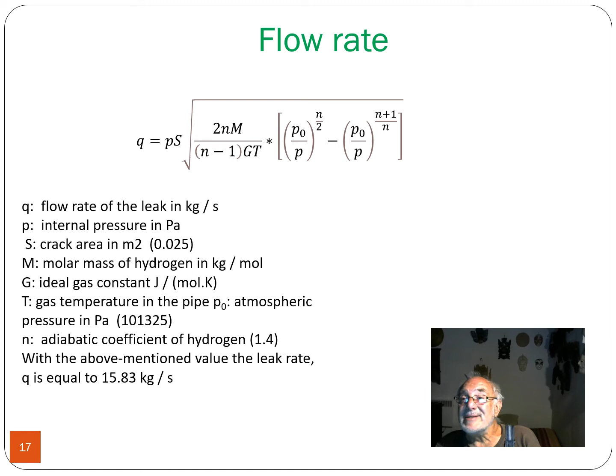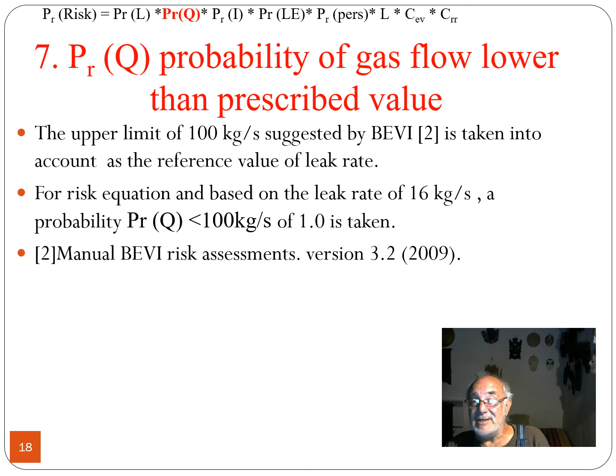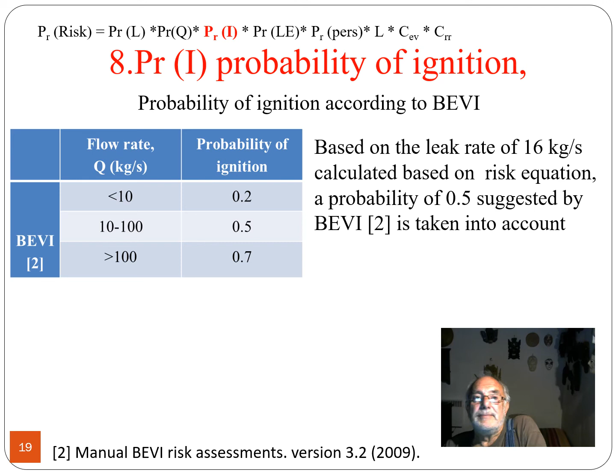Now we compute the probability of a gas flow lower than a prescribed value. An upper limit of 100 kg per second has been suggested by BEVI, with the reference given here. For the risk equation, and based on the leak rate of 16 kg per second as computed previously, a probability of gas flow less than 100 kg per second is taken as unity. The probability of ignition is also calculated from the recommendation of BEVI. In the following table, we have the correspondence between the flow rate and the probability of ignition. You can see that with a computed value of 16 kg per second, the probability of ignition of 0.5 is given and suggested by BEVI.